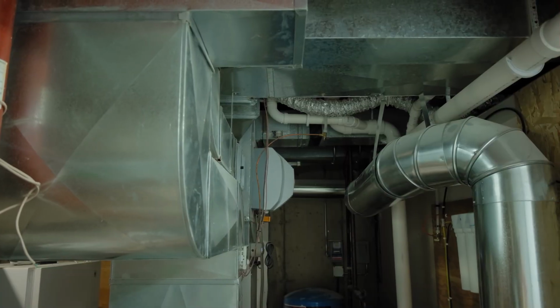And so just a quick note, as we're taking measurements, I am not going to spend time analyzing each individual data point or absolute value. So if I'm getting a static pressure of 0.3 inches on our MERV 2, not really going to mean much until I have a chance to compare it to the statics of the other filters. And a big part of that is because everybody's HVAC system is designed differently between ductwork, furnace sizing. Those are all factors that can impact the measurements that we're getting.